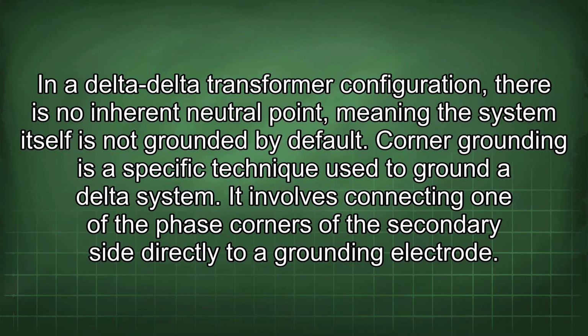In a delta-delta transformer configuration, there is no inherent neutral point, meaning the system itself is not grounded by default. Corner grounding is a specific technique used to ground a delta system. It involves connecting one of the phase corners of the secondary side directly to a grounding electrode.